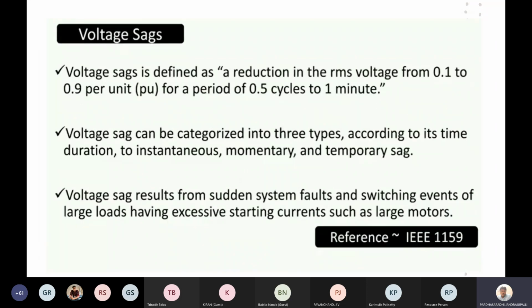Similarly, voltage sag. We already discussed under voltage and over voltage, which are different from voltage sag and voltage swell. Voltage sag is defined as a reduction in the RMS voltage, from 0.1 to 0.9 per unit, for a period of 0.5 cycles to 1 minute. Usually, if the voltage problem stays for more than 1 minute, it is said to be under voltage, but here the time boundary is from 0.5 cycles to 1 minute. The magnitude is also clearly mentioned according to IEEE, from 0.1 to 0.9 per unit. Voltage sag can be characterized into three types according to its time duration: instantaneous, momentary, and temporary. That is, how long they stay, whether 5 cycles, 10 cycles or 1 minute.